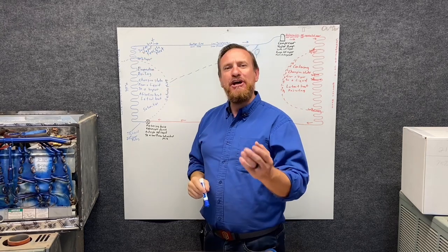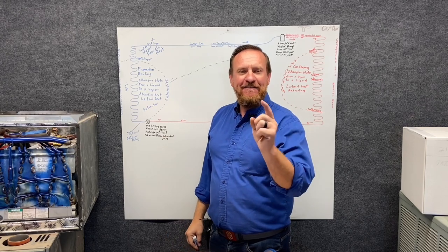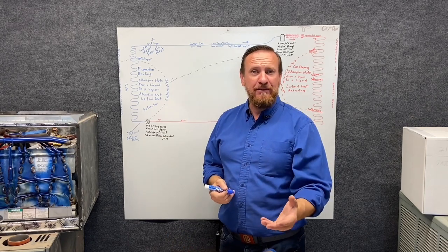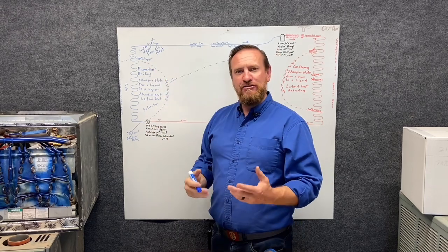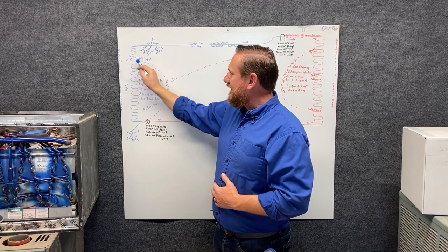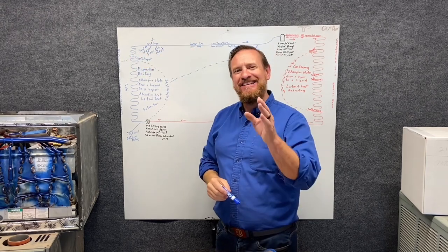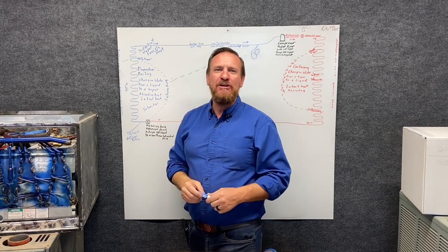This is a measurable heat. This is called superheat, superheated vapor. So at this point, anytime you talk about vapor, say a superheated vapor. So it's going to be a superheated vapor and it's sensible. So in our refrigeration cycle, we're going to add the words right here, at the very top of the evaporator, superheated vapor, and that's a sensible heat, which is measurable. Sensible heat and measurable heat go hand in hand.